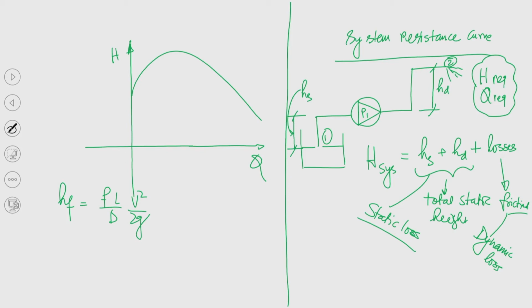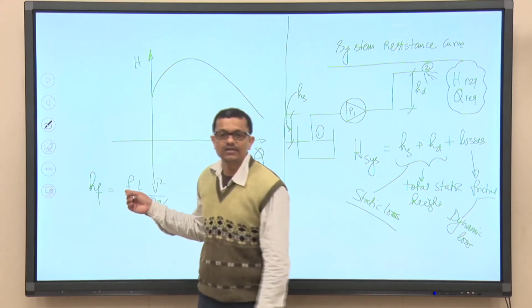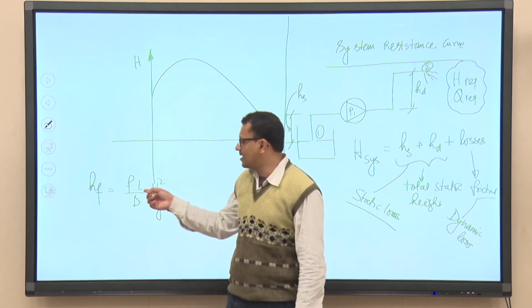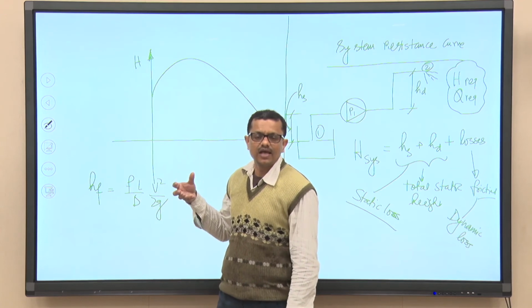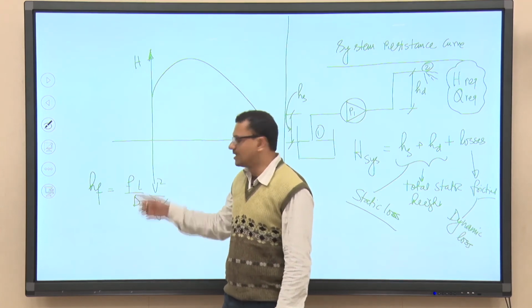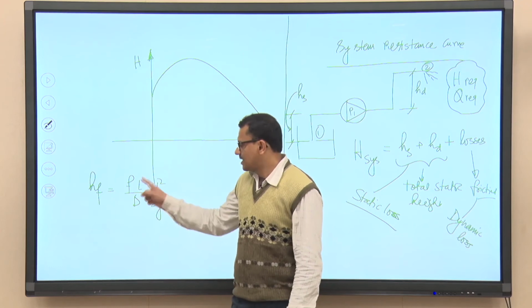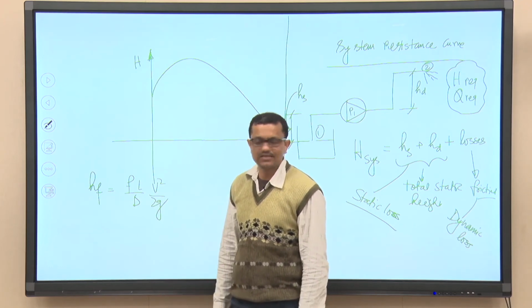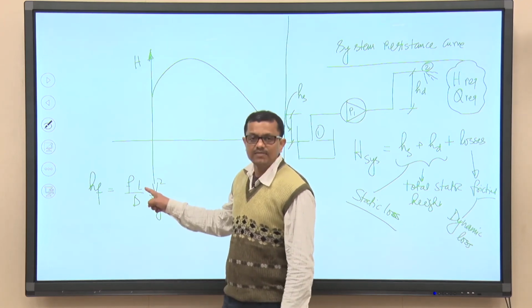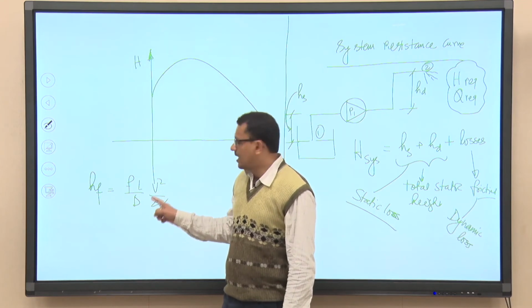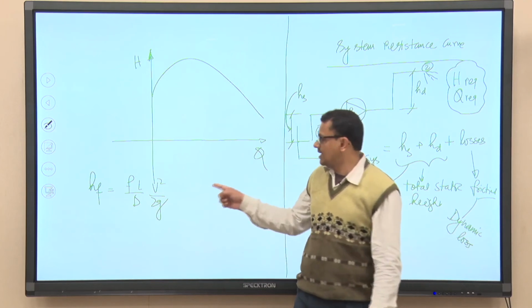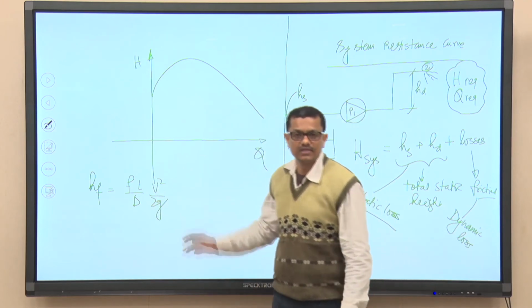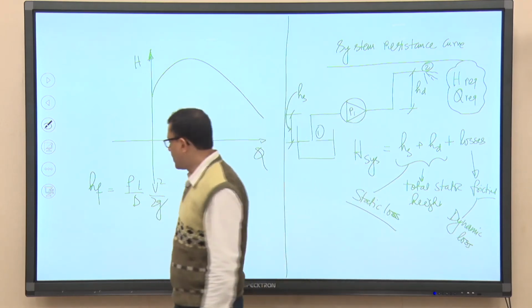Now, if it is laminar then fine, but in most cases flow is not laminar. So, we need to consult the Moody's diagram to find the friction factor, because if we know the roughness we can easily get the friction factor from the Moody's diagram. We know the length of the pipe and also the diameter, and if my requirement is Q required, then I can easily calculate the velocity at both the suction and delivery line, fine.